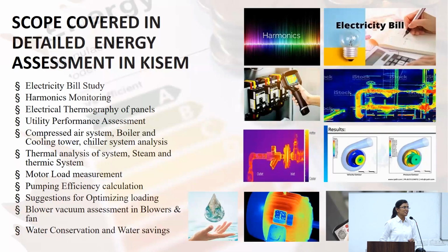Next, for the thermic fluid system, industries also have thermic fluid heaters. In those heaters also, we examine the flue gas analysis. In the flue gas analysis, we examine what the O2 percentage is, and what the combustion efficiency is, taking direct and indirect as well. Next is motor load measurement. We also do motor load efficiency testing, and check what the current motor load is. For example, if any motor is running at less than 30% of load, we will recommend how to improve your efficiency without affecting your process.